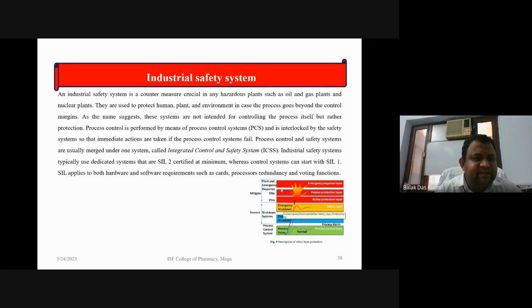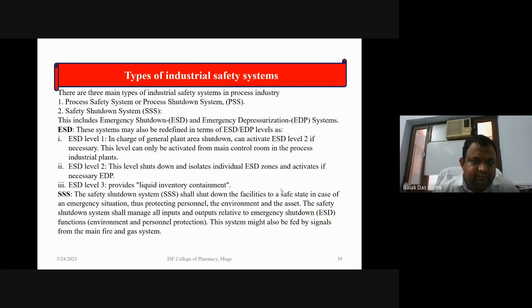Process control and safety systems are usually merged under one system called the integrated control and safety system. Industrial safety systems typically use dedicated systems that are SIL2 certified at minimum, whereas control systems can start with SIL1. SIL applies to both hardware and software equipment such as cards, processors, redundancy, and voting functions. So there are some types of industrial safety systems, which include the process safety system or process shutdown system, PSS, and the safety shutdown system. This includes emergency shutdowns and the emergency depressurization system, EDP.